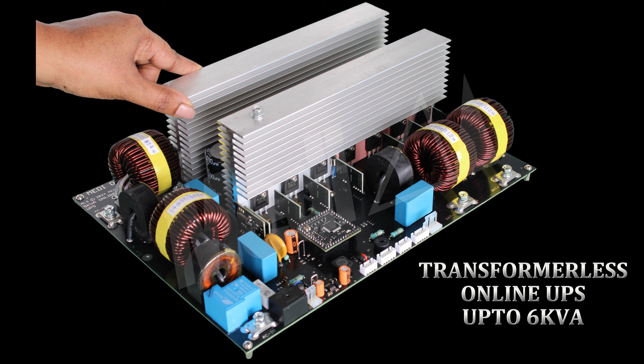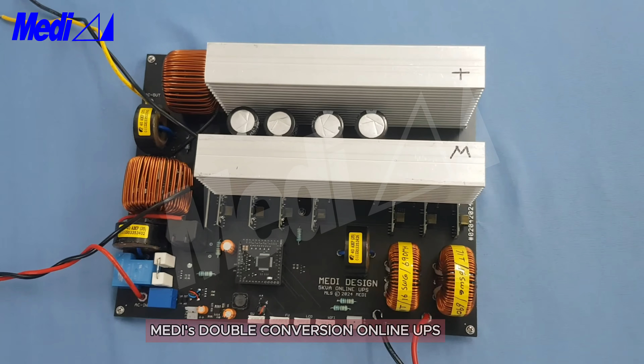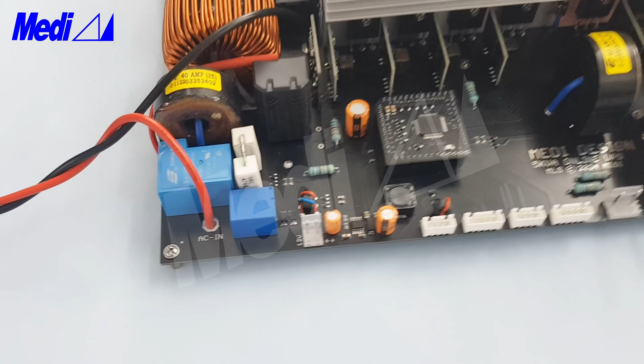This is Medi's double conversion online UPS up to 6 kVA. Transformerless multi-level switching topology with active power factor correction and current harmonic reduction with static bypass. This is a compact design with very few components, easy to assemble and extremely low cost.